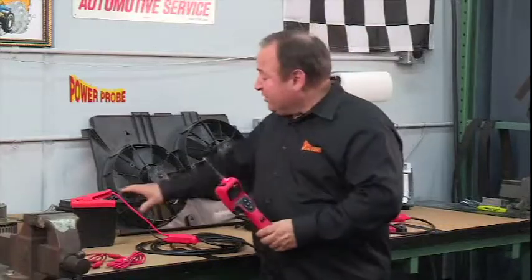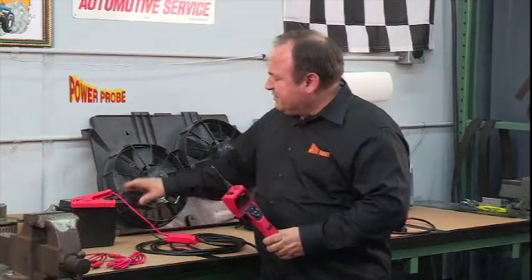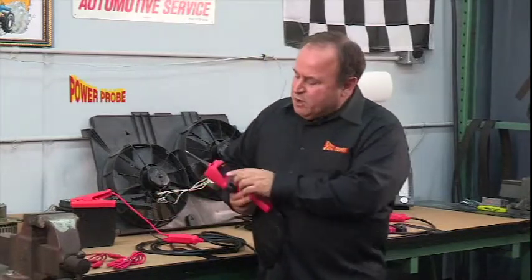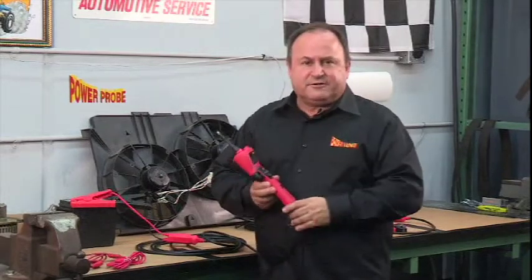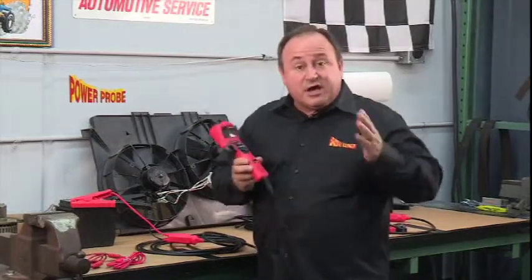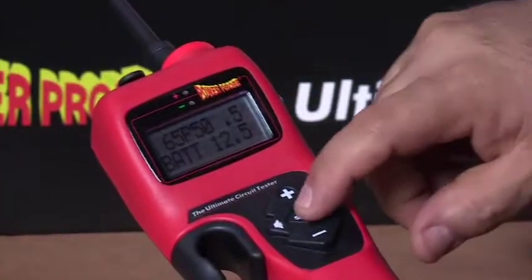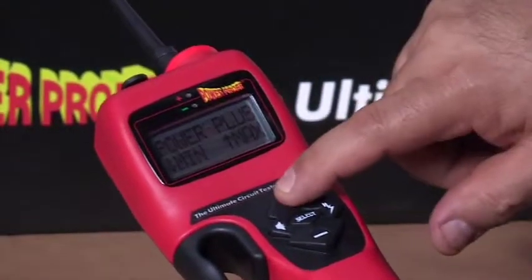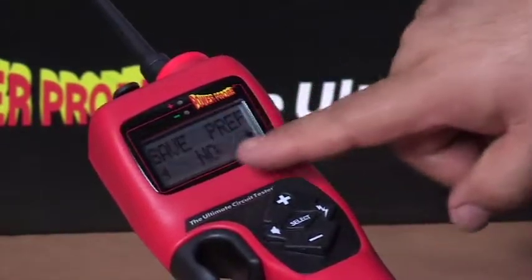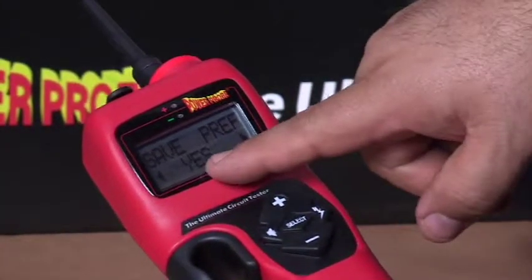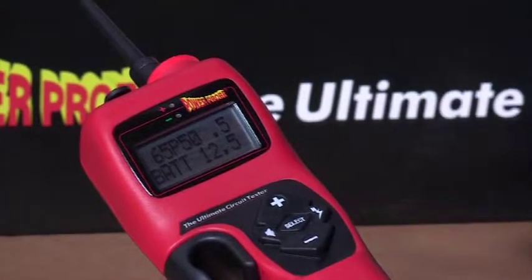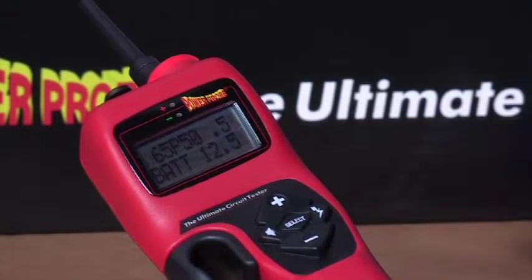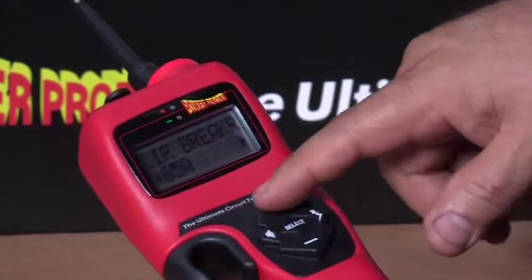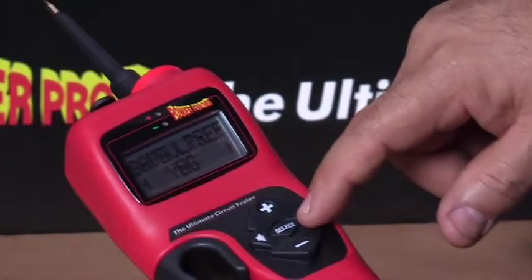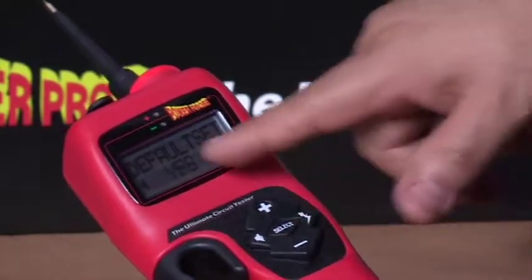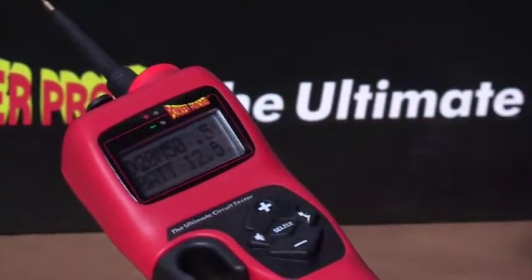Now, when you disconnect the power lead from the battery and then you reconnect it, the PowerProbe Hook defaults back to its original preferences. Now, if you want to keep your custom settings, do this. Press select and then the up button twice. The display reads Save Pref. Press the right button once and then select again. To reset your preferences back to factory default, do the same thing as I just showed you. Just choose Reset Back to Default and then Yes, then press Select.